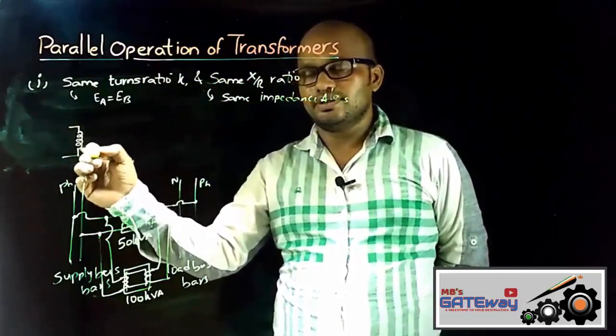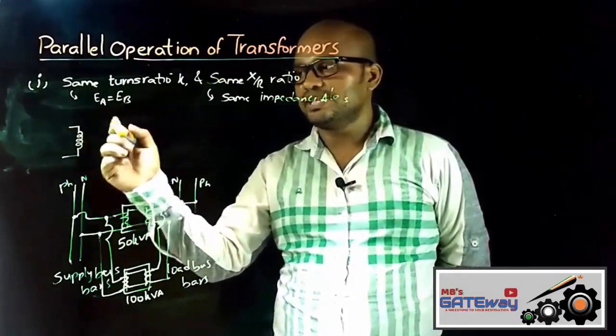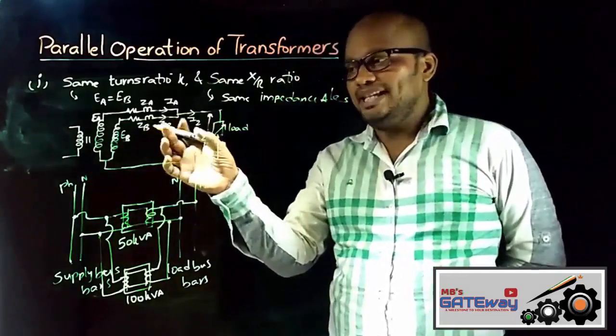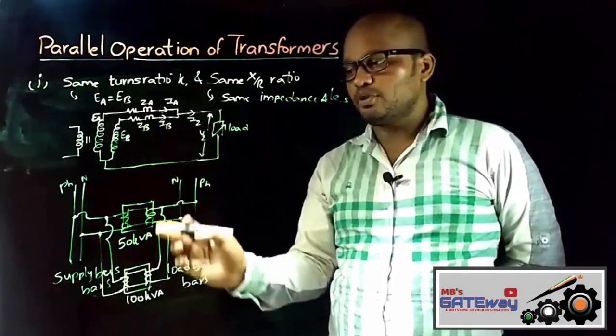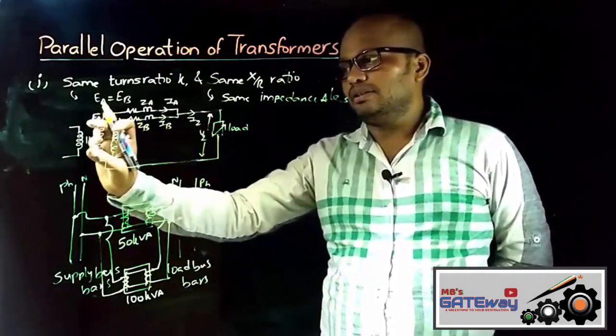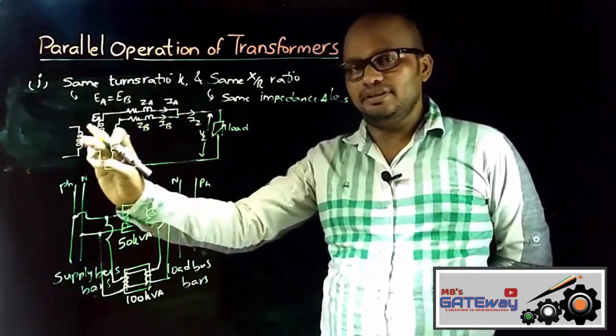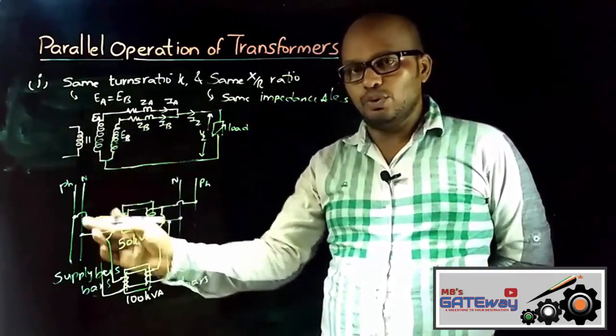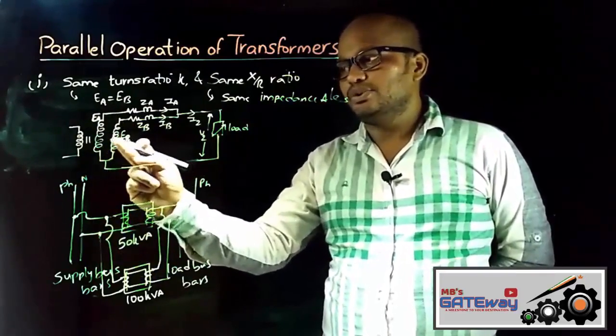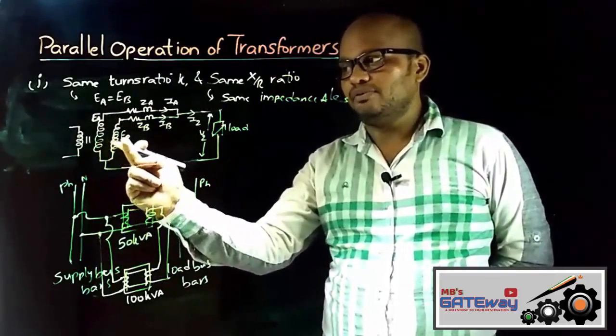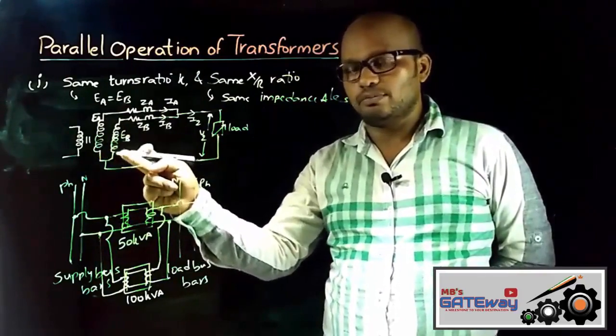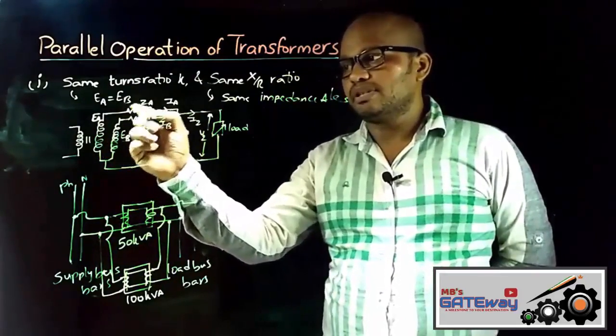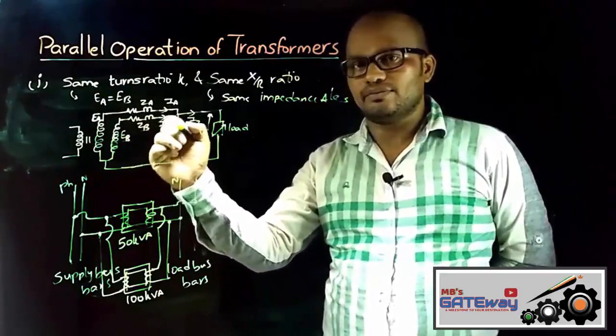This together represents the primary winding of both transformers, and this represents the schematic diagram of two transformers operating in parallel. This winding represents the primary winding of both transformers, and these two represent the secondary windings of transformer A and transformer B. This is the impedance of transformer A and this is the impedance of transformer B.